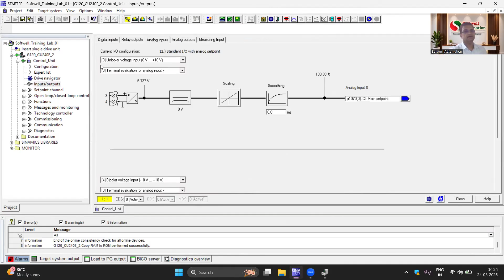So right now, proper scaling is done and only the test is required. So I'm going to click the start command. What is the best option? One is physically, and also we will check after clicking input output, and first tab digital inputs, and this one is the first terminal. Also green color represents that physical wiring is available. So I'm going to click the start tab. So first time, if you click the start, and right now all the motor data is entered, a motor ID test is also required. So after giving the start command, first we have to go for the test auto tuning.